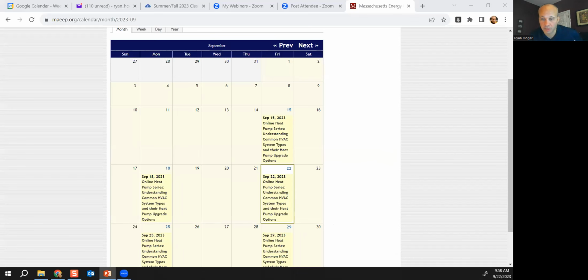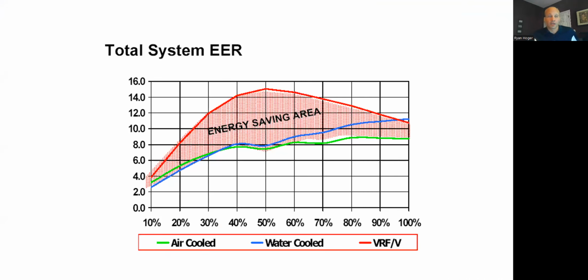Oh, we're actually good. Only like 3 more slides of importance here. Okay. This is just showing you an example, and this can be different for every kind of machine. But at the time, this is probably like 6, 7 years ago, this green line was the minimum legal code efficient chiller. This is the minimum legal air or water cooled version of a chiller, right? And then this red line was a standard VRF system, right?